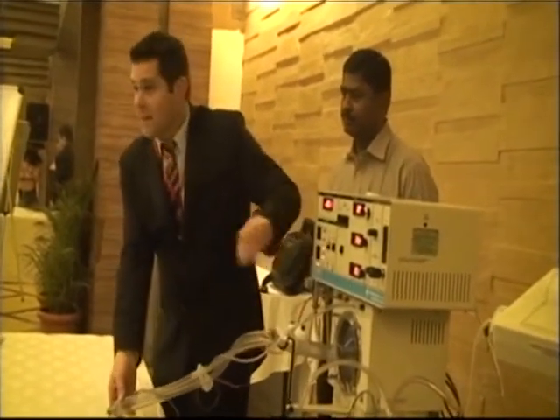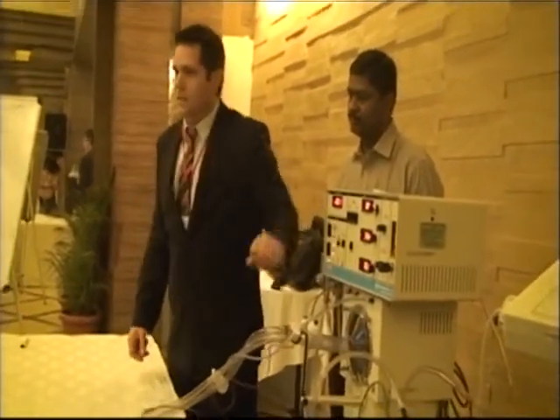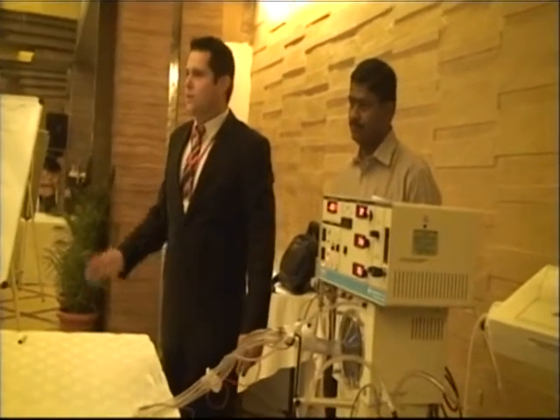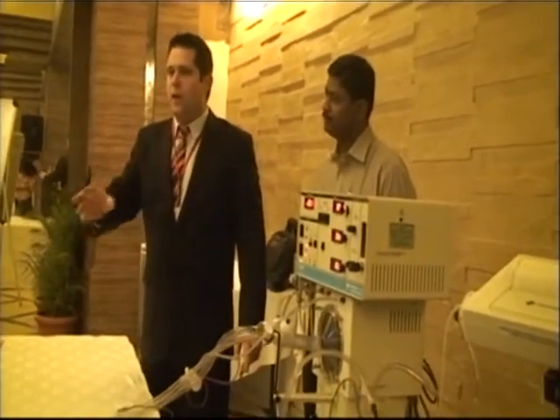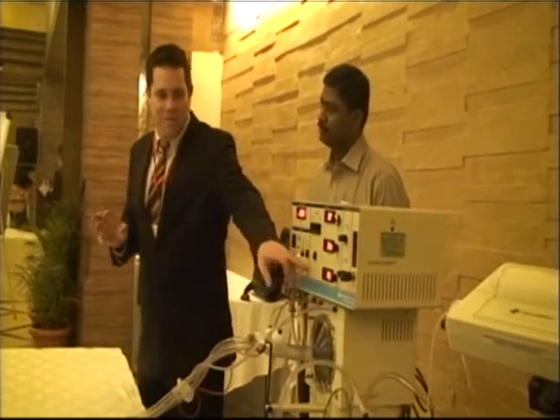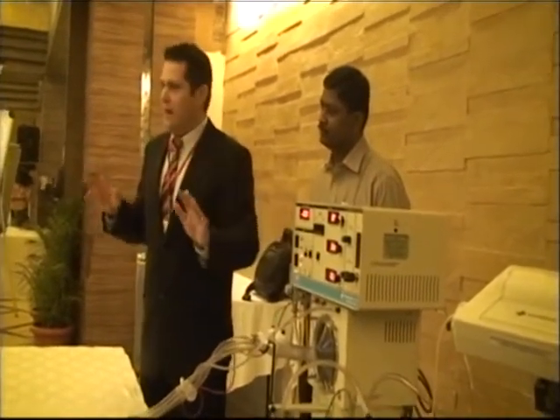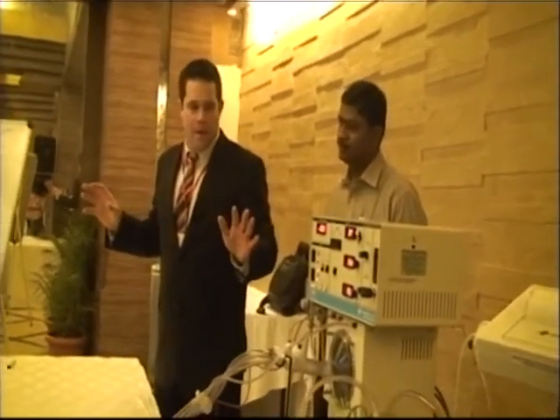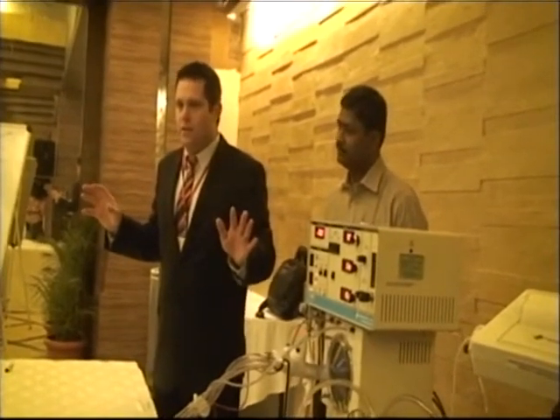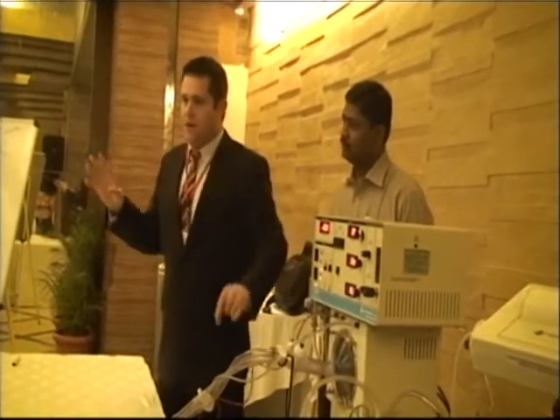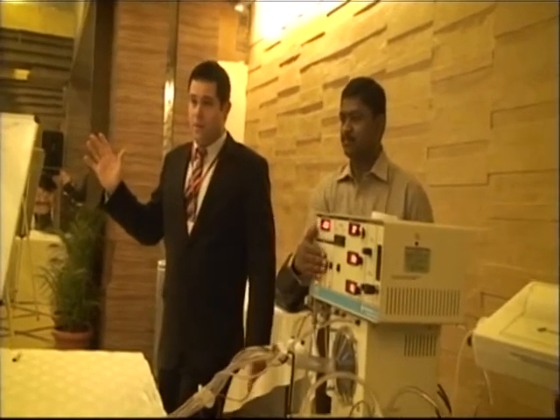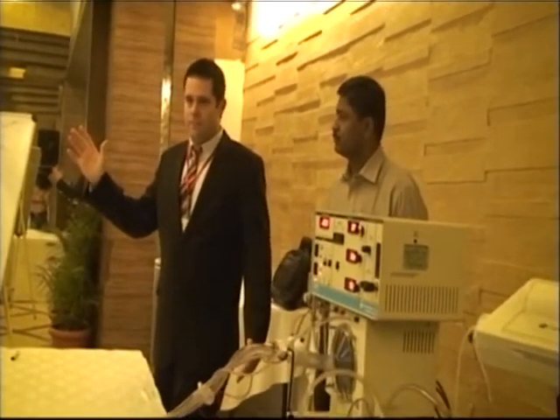Now, the last setting on the ventilator is your frequency setting. This is where most people become confused. If you can overcome this simple terminology, you'll understand high frequency oscillatory ventilation. Most premature babies, we will start their Hertz setting at around 12. If they're low birth weight babies, we'll start them at 12 to 15. If they're term babies, we start at a 10 to 12 Hertz setting.